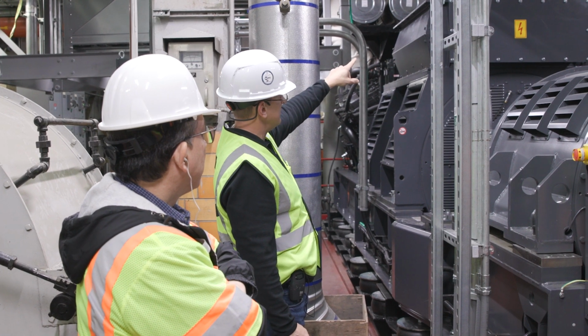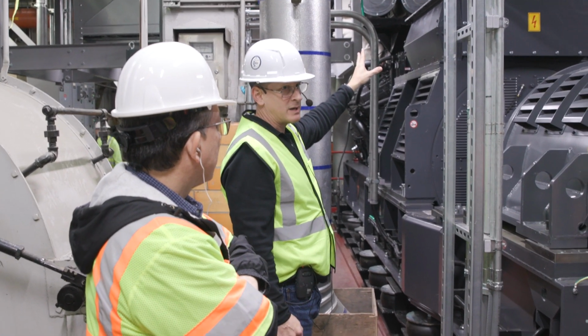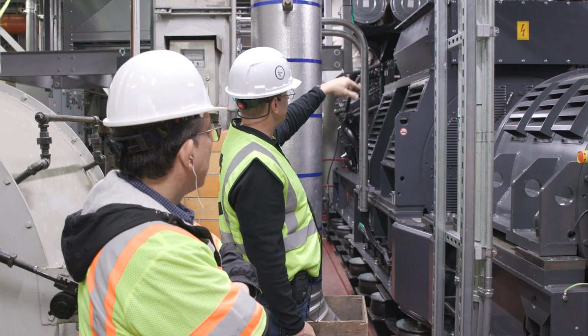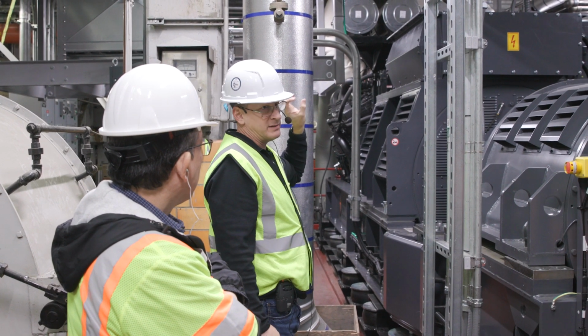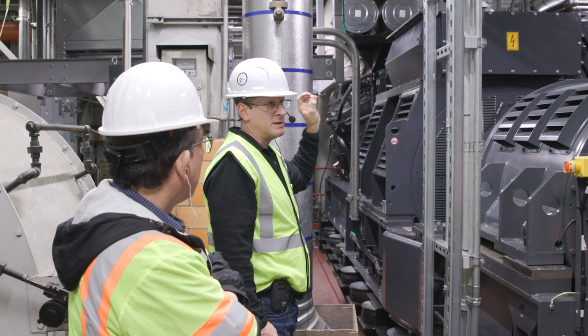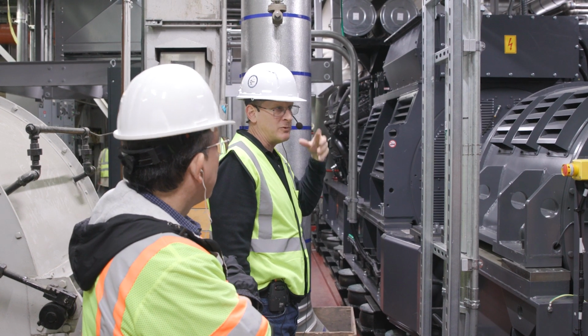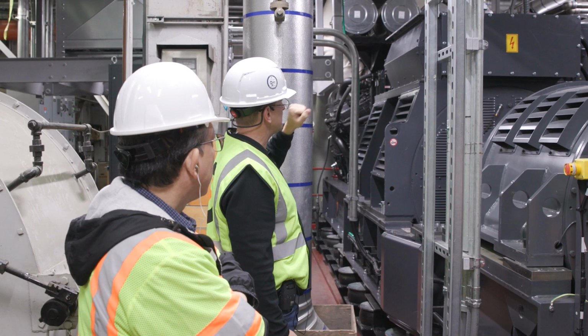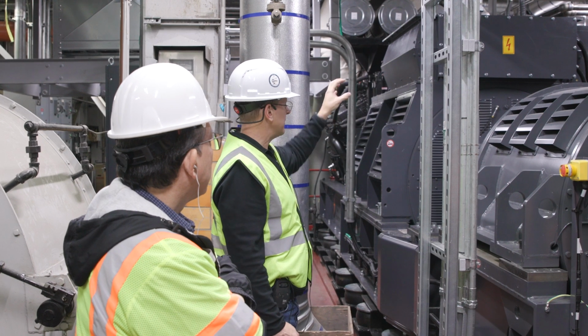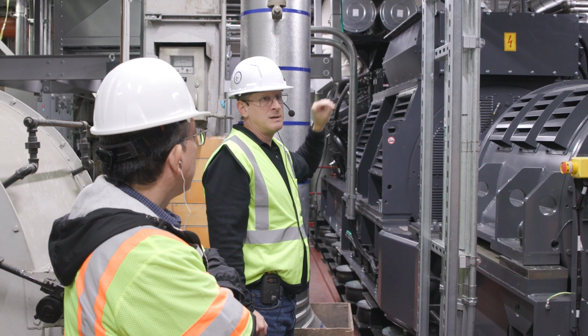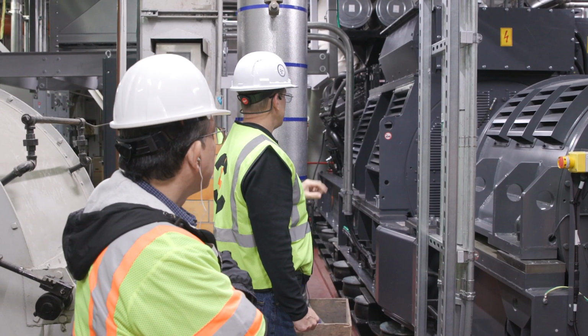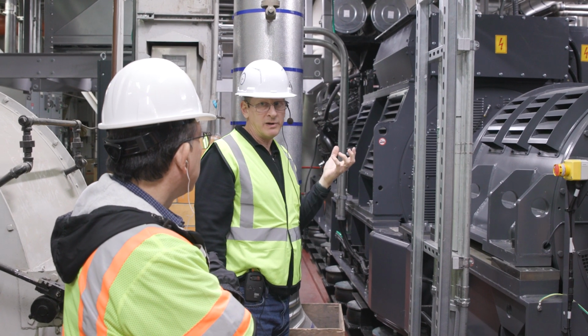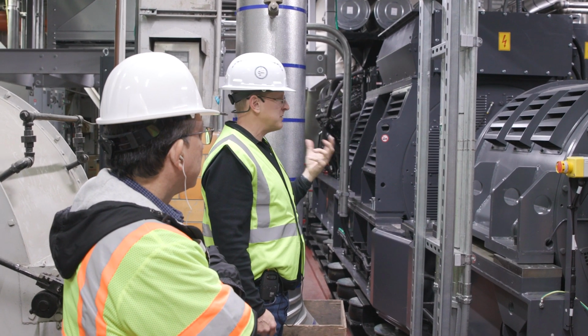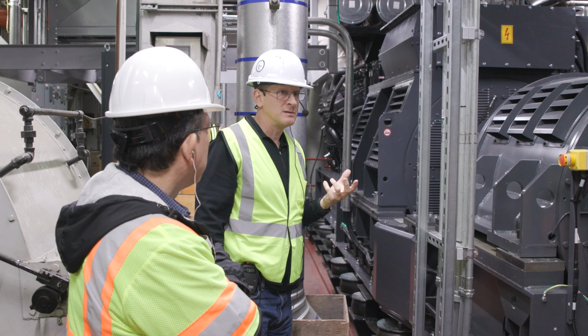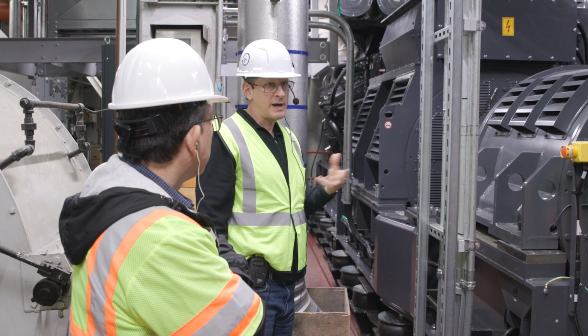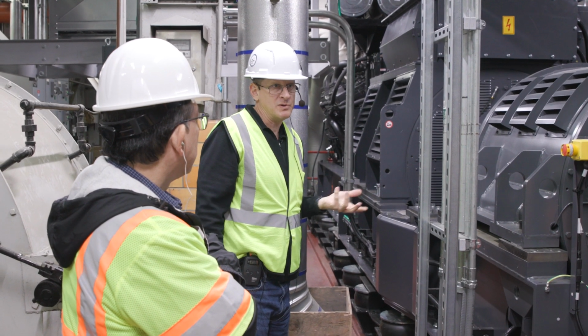On the top of the alternator itself, you'll see the generator junction box. And there's a little window there on the left side. That window is actually looking at the AVR. So there are some light indications on the AVR that will show some alarms. You can see those through the viewing window. But the AVR is located inside that box, where it basically states it is a digital AVR. It has its own protections against overexcitation, much more advanced than the old style analog AVRs that we've used in prior generations.